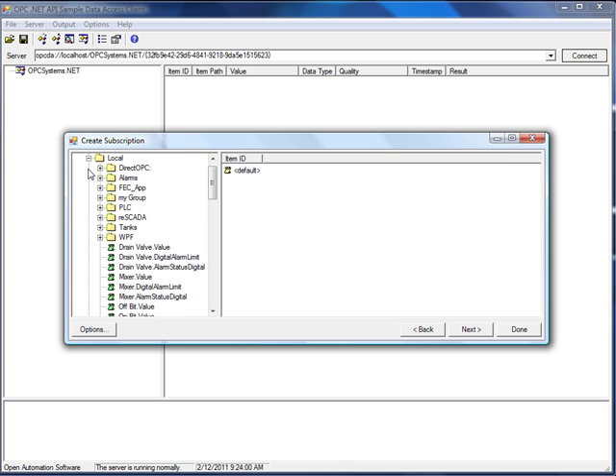When you're browsing remote services, if you want to use an IP address, you'll have to manually enter that into your OPC item path. But you can use the network node to get an example of what that's going to look like for a remote connection. On the local service, I see all of the opcsystems.net tags that are defined under Configure Tags.